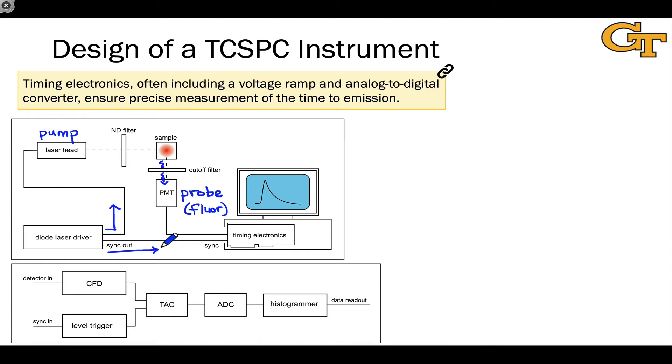This avoids scattering issues of the incident light and other emissions that may not be directly relevant to fluorescence. And that photon is detected at the photomultiplier tube. At that instant, we get a signal back to the computer that says, turn off your stopwatch and record the time that has elapsed. And what actually happens is that voltage ramp is stopped. And then a time to amplitude converter converts the voltage signal into a time. An analog to digital converter puts that time in digital form. And then a histogrammer essentially plots that time, adds that time to our running histogram of times to emission.